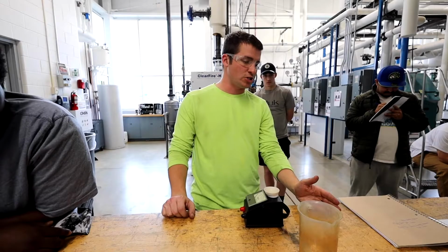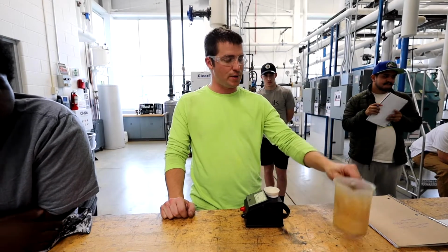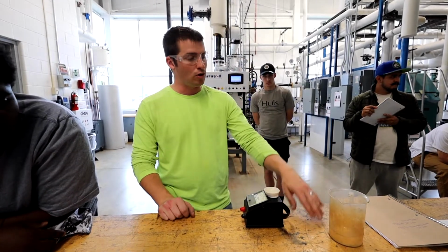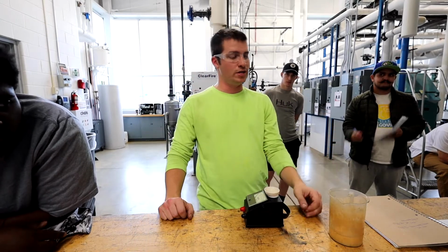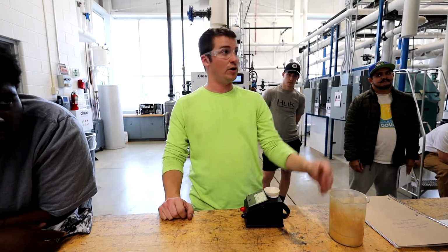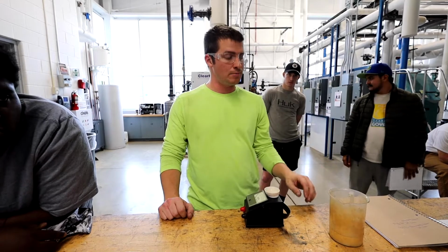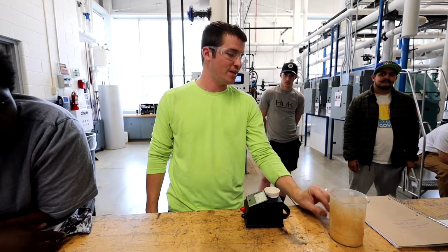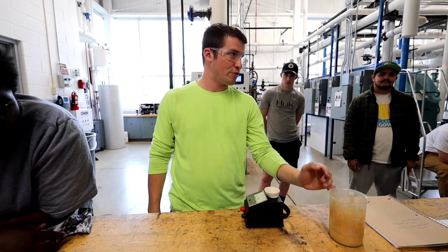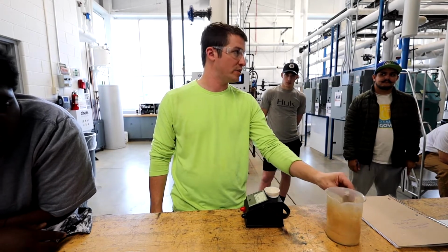So cycles of concentration, easiest way I can explain that is if this is a pot on your stove at home, right? You boil all the water off. You get the little white residue left in. You fill more water up, you do it again. You get more white residue, you do it again, right? So if you do it 3 times, we would say you have 3 cycles of concentration because you've taken what was originally in that water and have now concentrated 3 times in there because I did it 3 times over.